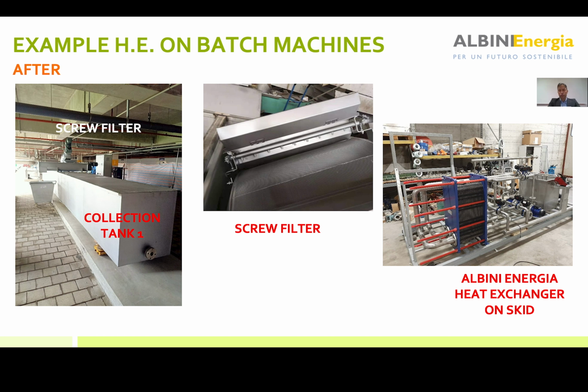the reason why we chose the plate heat exchanger, an economic solution, because you will see later on the number of working hours and the flow of the system was not big enough to have a good payback with the pipe shell heat exchangers. So we prefer to add the screw filters on both sides in order to guarantee the plate heat exchanger that we have actually used. And in this particular case, both sides of the heat exchanger are cleaned by chemical systems.